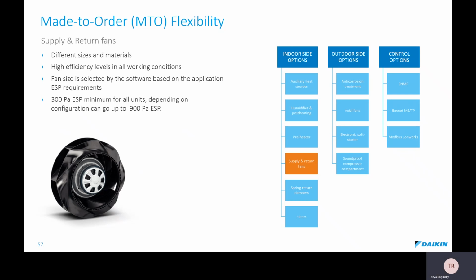On the fan selection, we have a variety of optional choices. We have different sizes and materials for any application. High efficiency levels in all working conditions. Fan size is selected automatically by the new selection software based on the external static pressure requirements. 300 pascals is the minimum for all units. And depending on configuration, you can go up to 700 pascals or 900 pascals if required.